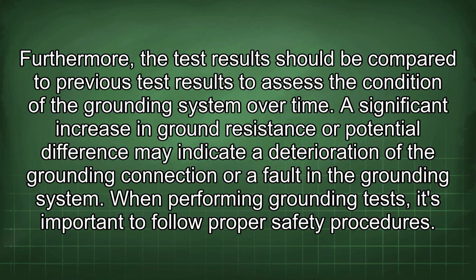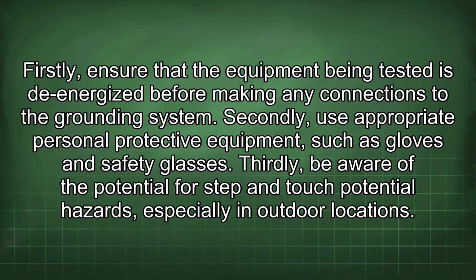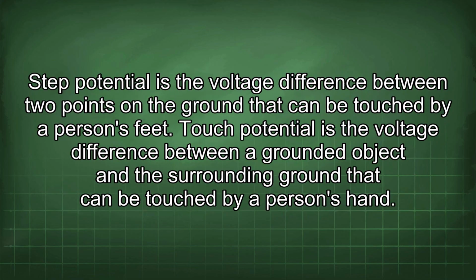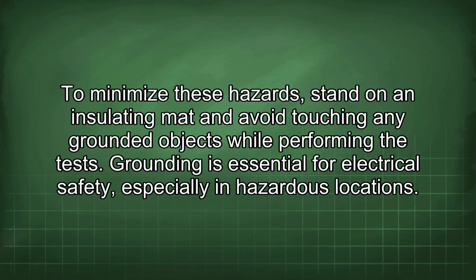When performing grounding tests, it's important to follow proper safety procedures. Firstly, ensure that the equipment being tested is de-energized before making any connections to the grounding system. Secondly, use appropriate personal protective equipment, such as gloves and safety glasses. Thirdly, be aware of the potential for step and touch potential hazards, especially in outdoor locations. Step potential is the voltage difference between 2 points on the ground that can be touched by a person's feet. Touch potential is the voltage difference between a grounded object and the surrounding ground that can be touched by a person's hand. To minimize these hazards, stand on an insulating mat and avoid touching any grounded objects while performing the tests.